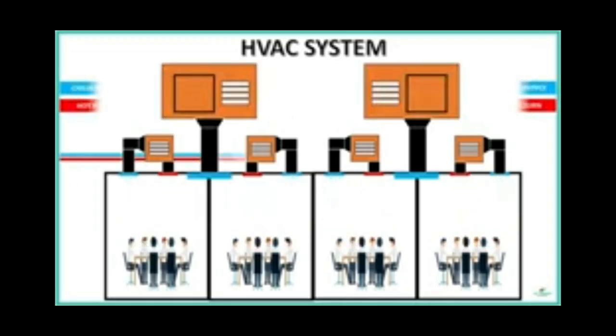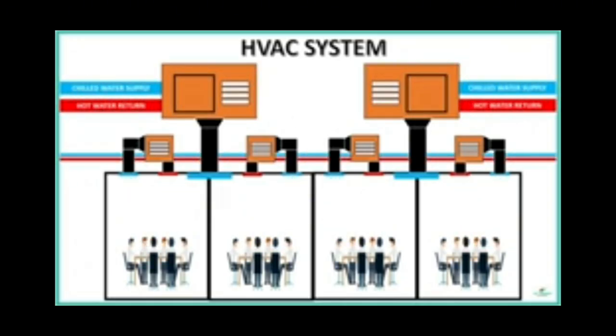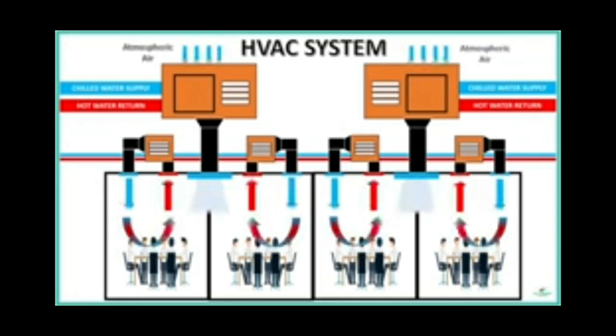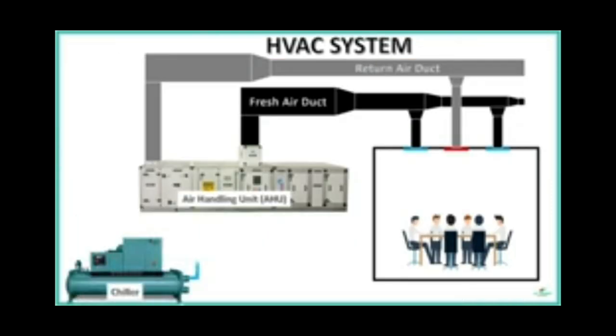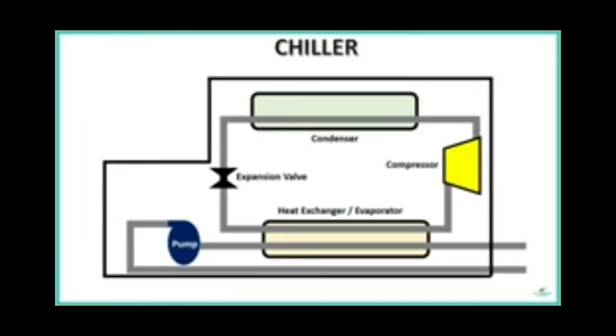Both the units consist of a cooling coil through which chilled water of the same condition is supplied to produce chilled air. Both the units work together in a smart way to replace the AHU for a larger environment and produce better results. So, where does this chilled water come from? A chiller is an electrical unit that produces chilled water by using the refrigeration effect. Typically, a chiller consists of a compressor, a condenser, an expansion valve, an evaporator or a heat exchanger and a circulation pump to circulate the water to the AHU.